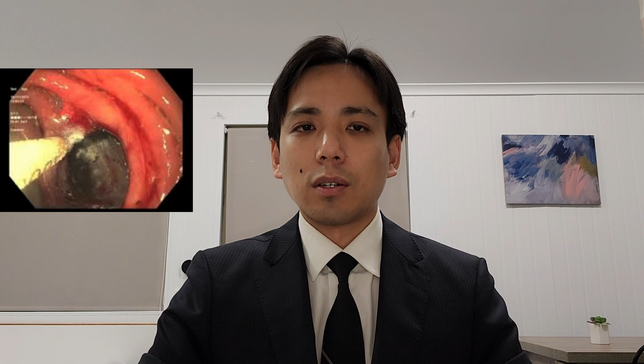APC emits argon ionized by a high voltage of 6,000 volts along a tungsten wire, resulting in a thermal energy field around the probe. This is a non-contact method of coagulation that covers a large area of up to 2 to 3 millimeters deep. APC has the advantage of being able to cover larger areas more quickly than a gold probe, and also looks much cooler when being used.